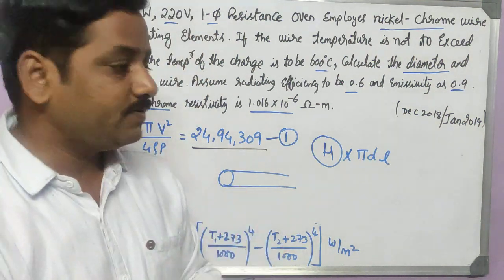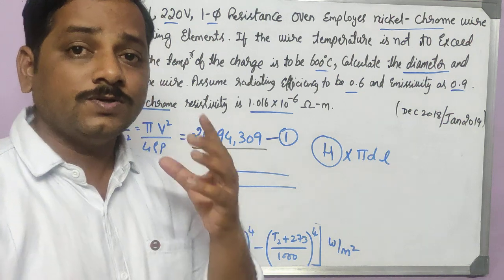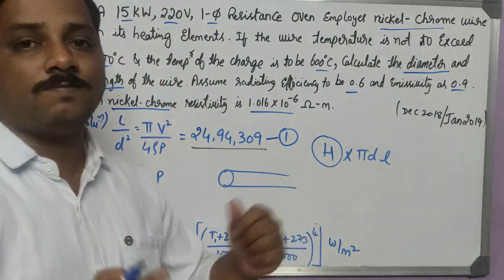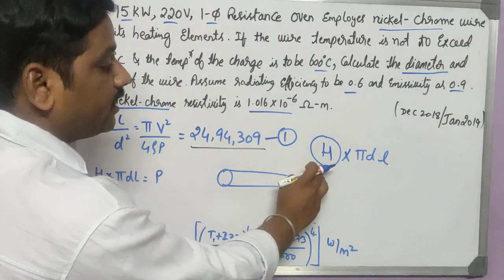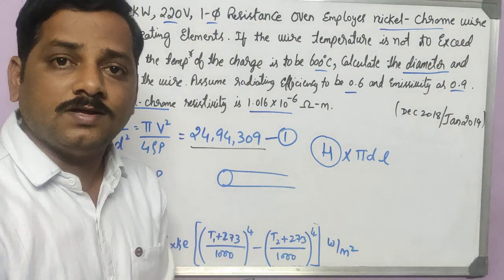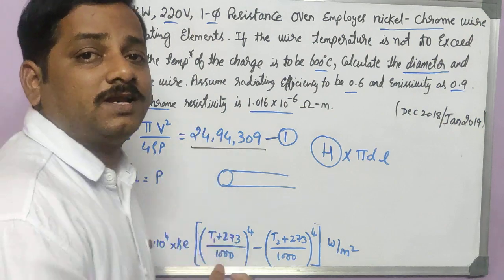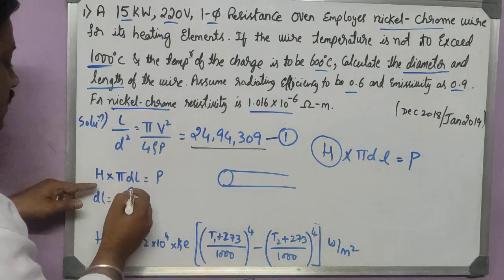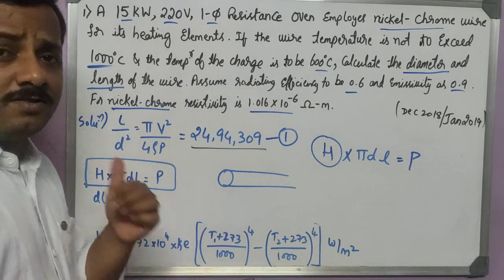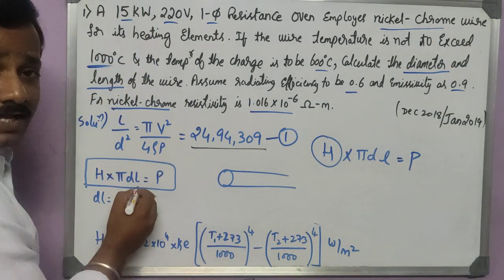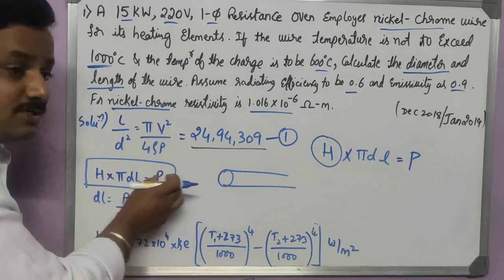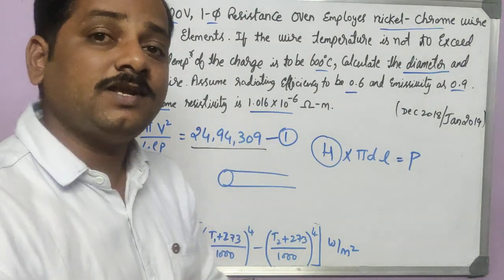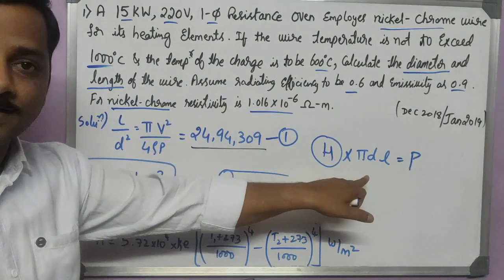If you have a circular type of coil, the surface area can be given as pi d L. If it is a strip, we get a different formula. That's why you need to identify whether you are finding a circular wire or designing for a strip. Based on that, the formula will change. Heat liberated per unit area into total area gives total heat liberated, and that should equal the power given. So H into pi dL equals P. That's what I have mentioned here. I will simplify this and get information for dL.